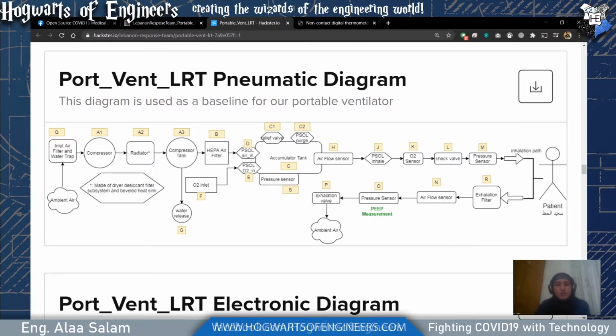And then we put it into a tank. Why? Always save your air in tanks, because you never know when something fails on this end or on the inlet. You cannot cut off the patient's breathing suddenly. You have to either open it to ambient air or provide air for a specific period of time.